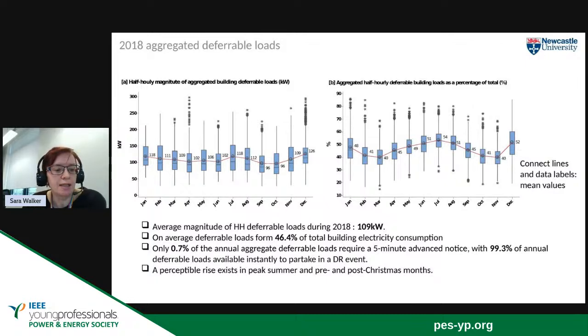So the overall aggregated demand response loads for the building and the percentage load does vary ever so slightly throughout the year because of that seasonality of the heat pump load. So again, slightly less availability in the spring and the autumn periods when there's just less heating and cooling load, but getting up to 54% of overall building load being deferrable in July, and close to that, 52%, in December. So a really significant opportunity for the building to do something rather than simply be a passive load on the system. And this is just using the heating, ventilation and air conditioning components of the building. This isn't accounting for anything that the storage in the labs might do or different control strategies that we might use alongside some of the generation.